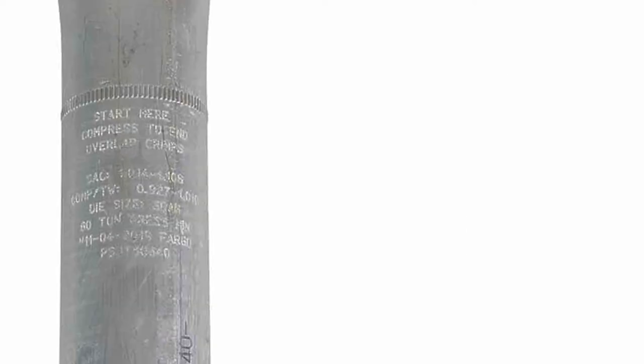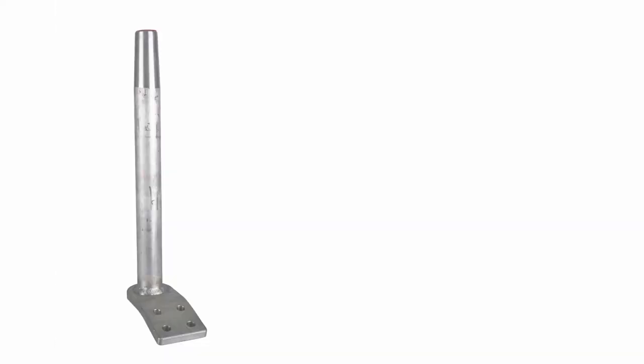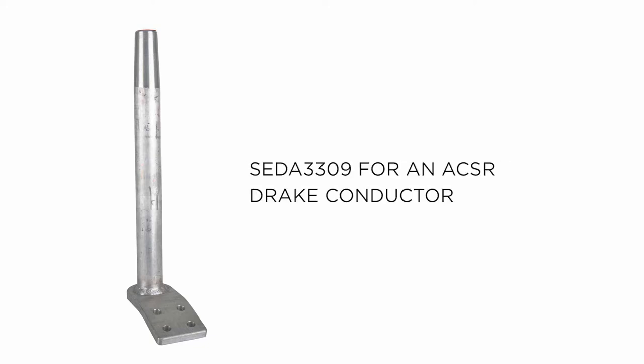The steel and aluminum components are stamped with die size, manufacturing date code, and Fargo catalog number. The aluminum dead-end body is also marked with a conductor size and type. In today's training we will be using a SEDA3309 for an ACSR Drake conductor.